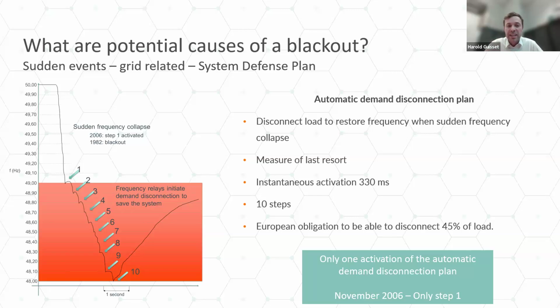Basically, if the frequency keeps dropping even after the first slice has been shed, then it's a second, a third, a fourth, and so on, until either the frequency stabilizes and we can go back to normal, or, if all those slices are not enough and we cannot shed enough load, the system would go into blackout, obviously. The frequency relays, which disconnect load, react in 300 milliseconds. It's extremely fast. It's not a human doing this. It's really frequency relays which measure the frequency and automatically disconnect the load if necessary.